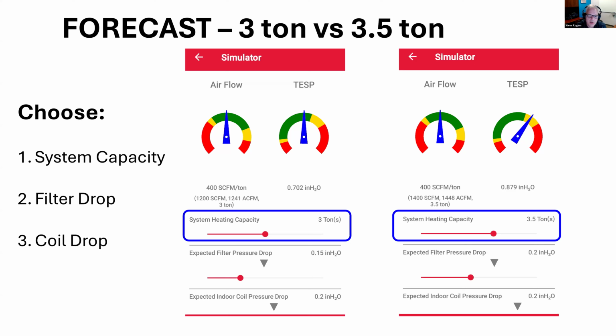But what you see here is that the 3 ton system on the left gets my airflow and my static pressure in the green. The 3.5 ton system, actually, the static pressure is too high. That's telling me that the existing duct system, with the information I've given about the new system, is not going to work. The static pressure is going to be too high, or the airflow is going to be too low, or both.